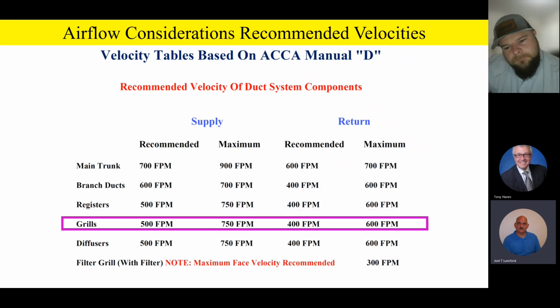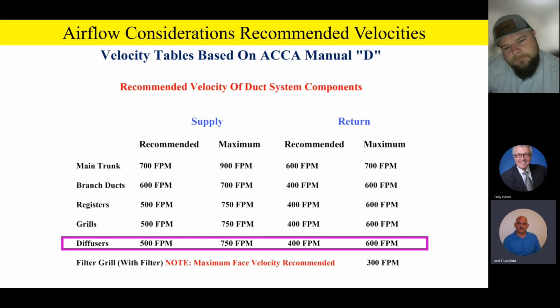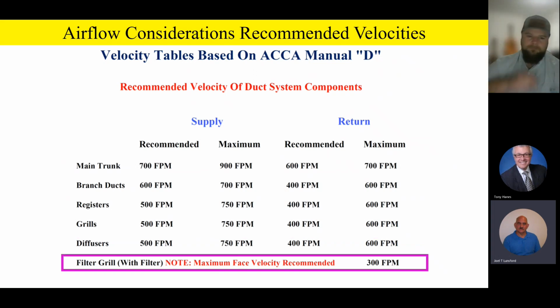And then return grills are going to be about the same, if you don't have a filter in it. Diffusers are going to be running right about the same feet per minute. Now, this is really, really important. Can't stress this enough. If you've got a return grill with a filter in it, you're going to want to make sure and size that filter grill no more than 300 feet a minute velocity. So we slow the air down quite a bit, from 500 feet to 300 feet a minute velocity, if we have a filter in that return grill.